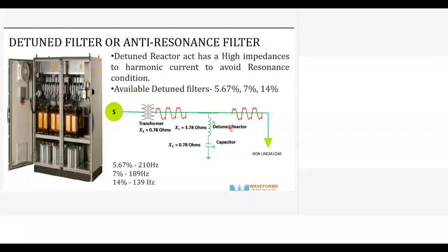We thought that 7% means it will block up to the 7th harmonic, and 14% for the higher ones. It is not like that. If you have the third harmonic, you can use the 14%. Oh, okay. 14% is expensive, so they go for 7% only, because normally the third harmonic is not dominant.